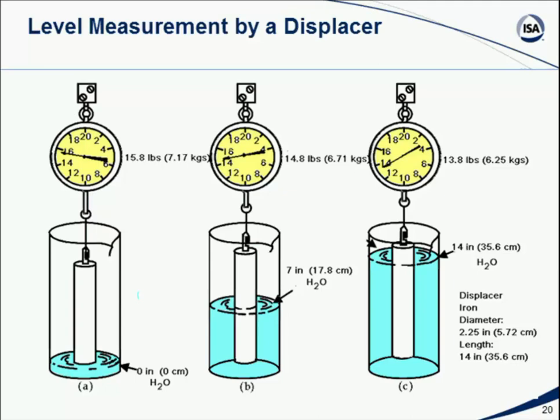Let's mention a simple fact: if you take an object and submerge it into a liquid, and you take the volume of liquid that it displaces and you weigh it, you will discover that the hanging weight of that object is reduced by the weight of the liquid it displaces. So if I have a cylinder, as this diagram shows, a hollow cylinder hanging from a weight measurement device, a scale of some type, and here on the left-hand side I'm showing a displacer, a hollow metal cylinder hanging in a tank, and there's water at the bottom of the tank, but the displacer is above it, we see that this displacer hanging in air weighs 15.8 pounds.